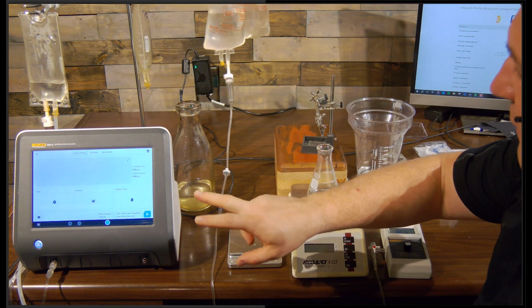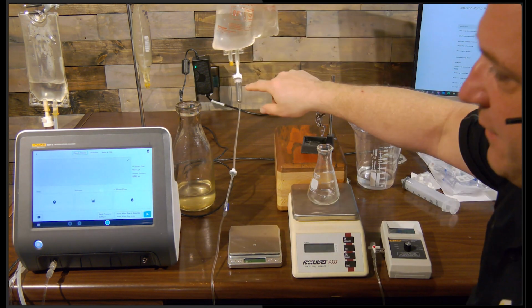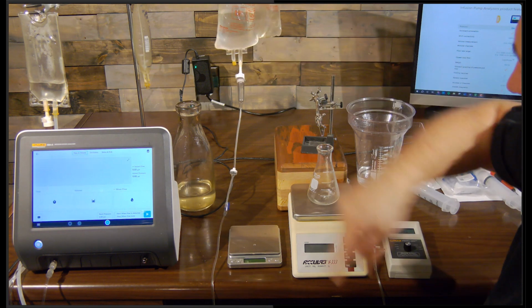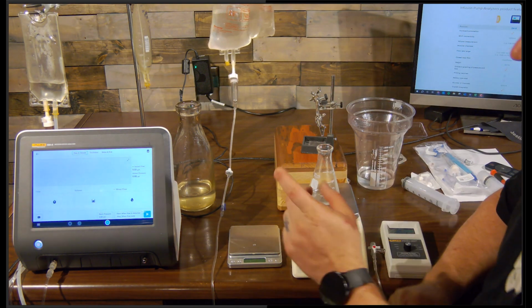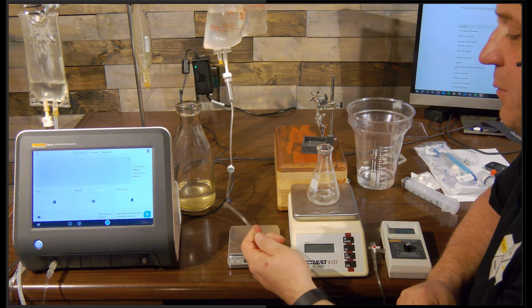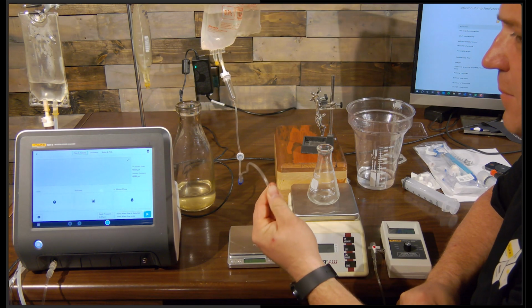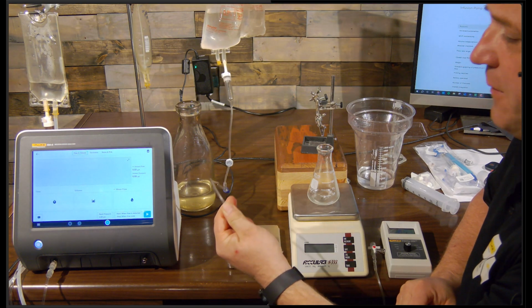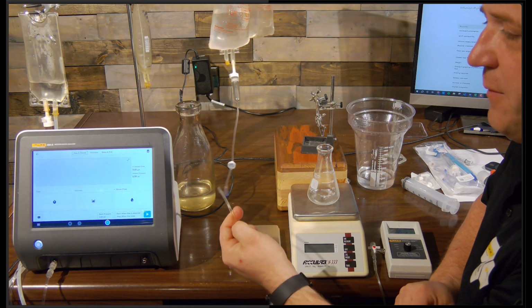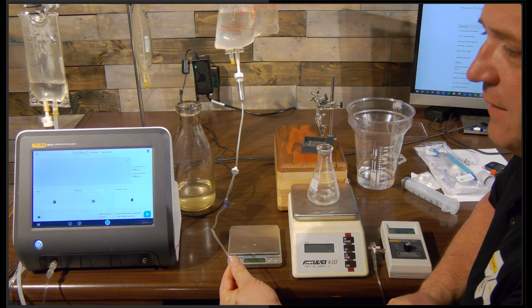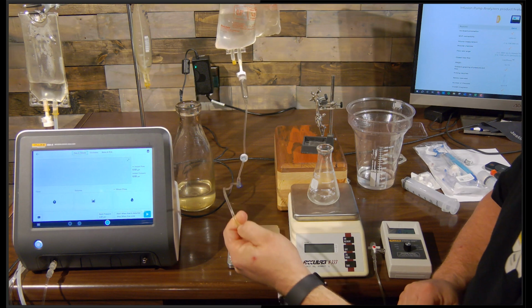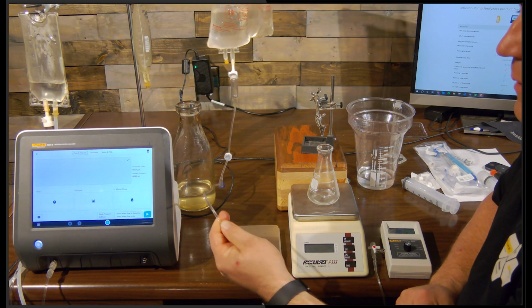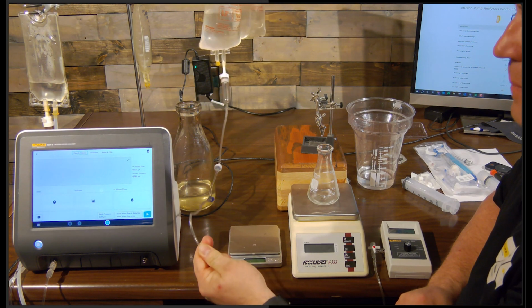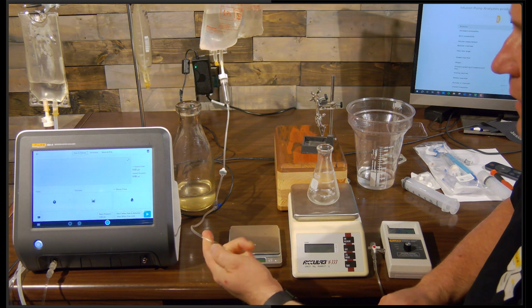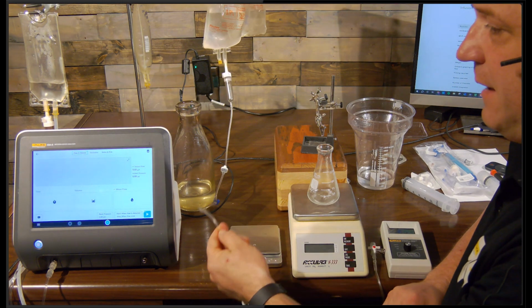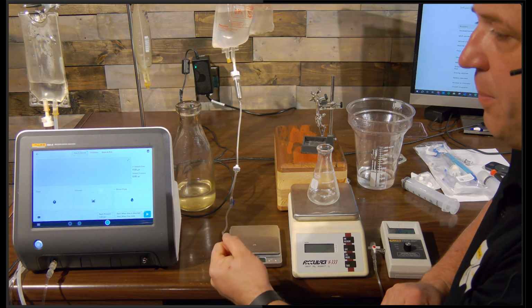There's two sets of IV tubing. If you're using two sets, you're going to have two bags to do this, and it's another test setup. But I find a lot of hospitals, when they use those two bags, feel that there's not enough of a variance in that calibrated test set, so they're just going to use one test set. They're not going to use the calibrated one. They're just going to grab one off the shelf. Some people say it's hard to get some of these test sets, so they just use a standard test set. Well, that adds yet more possibility of error.